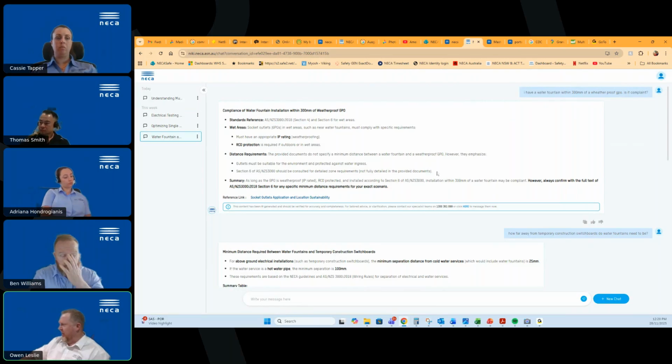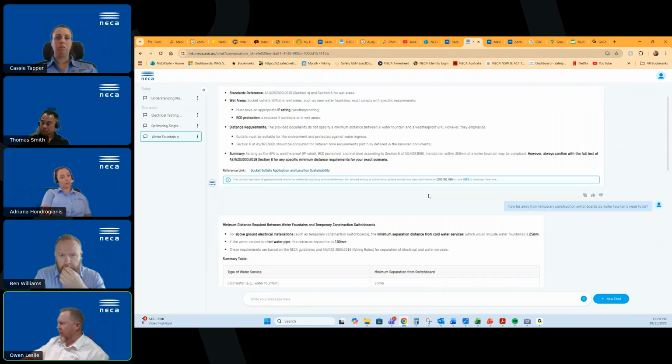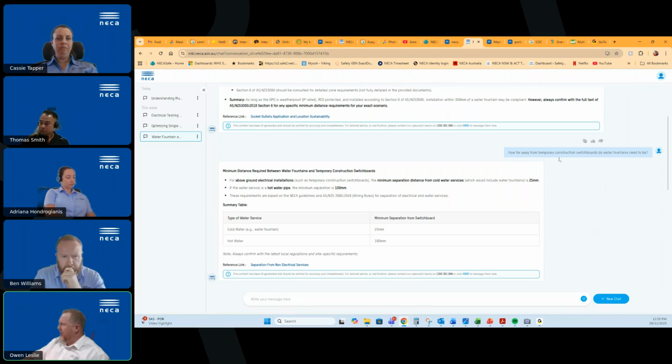So that was a pretty good answer, but I wanted to ask some more questions just to double check. How far away from a temporary construction switchboard do water fountains need to be? And it goes for above ground electrical installations, the separation 25 mil. If the water service is a hot water pipe, 100 mils, so it's not really answering the question that I wanted. These requirements are based on AS/NZS 3000.